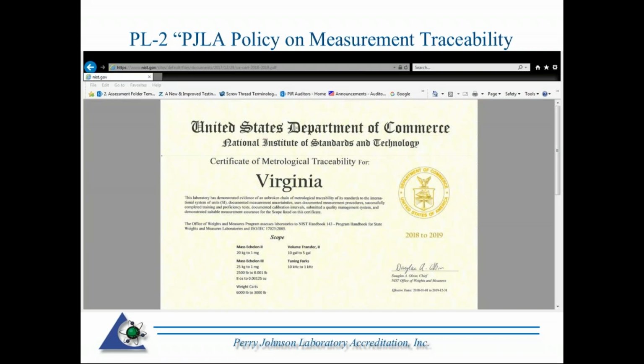I want to go to here because here's an example of a certificate of traceability from a state lab. You see areas of mass, volume here. With mass echelon 3, basically your industrial type scales, your commercial type scales. A lot of folks use the state labs for those types of calibrations. So when the program was started, it was mass, length, and volume. Some states, this one we're looking at here, actually expand into tuning forks. This is a little extra thing that they do there, which I know is a standard that they use for checking radar guns.